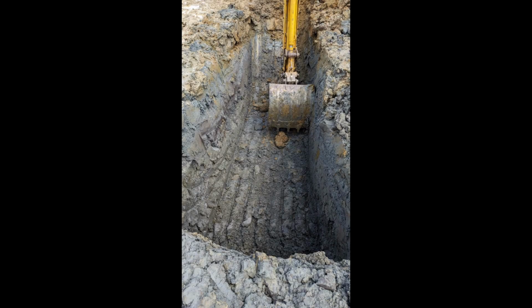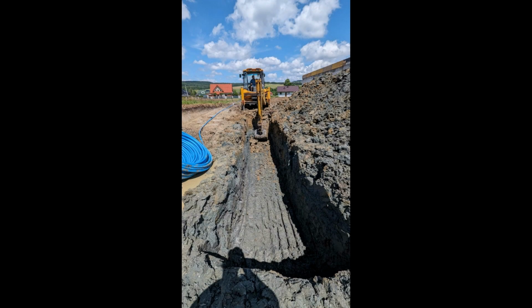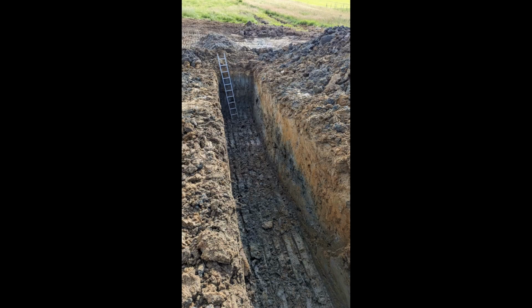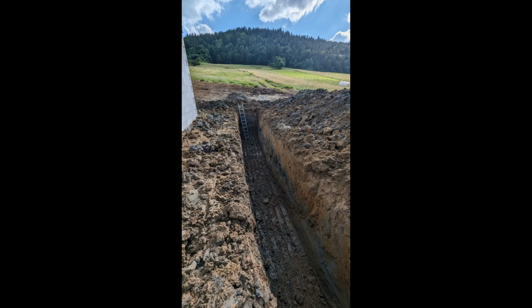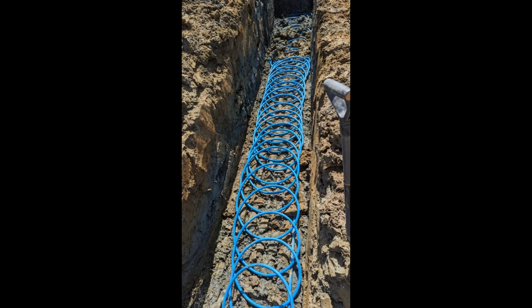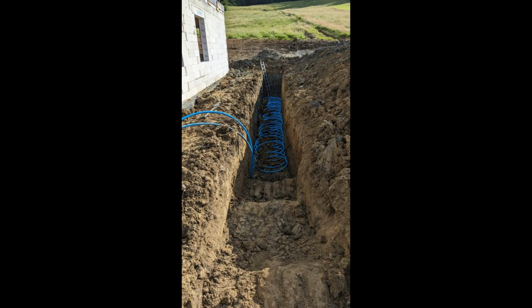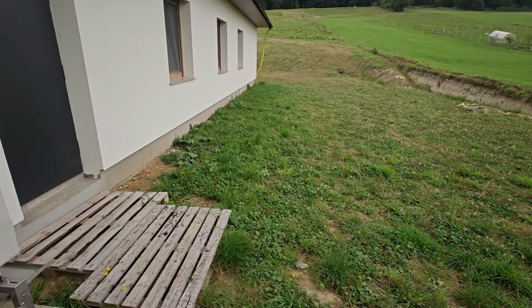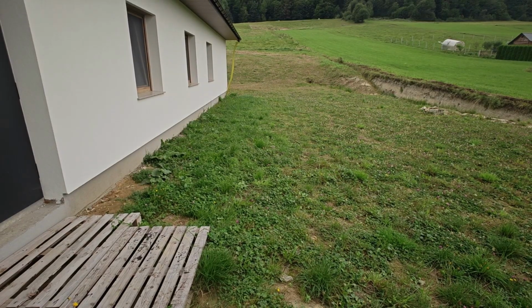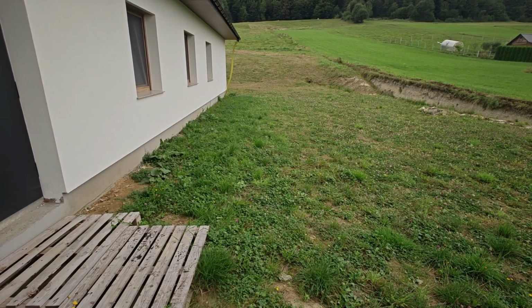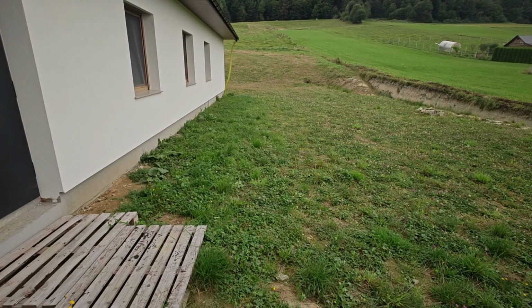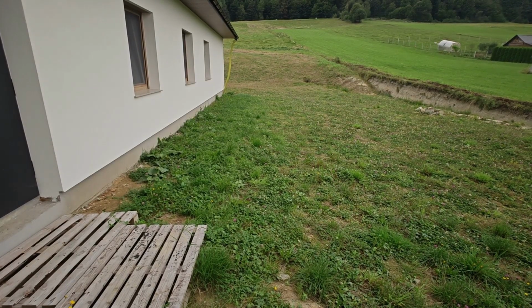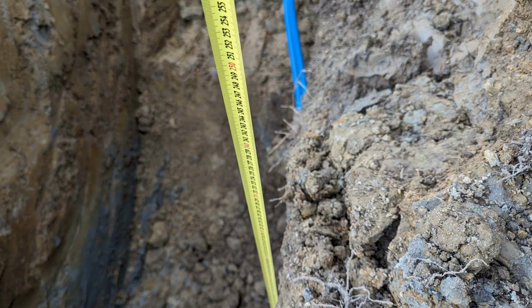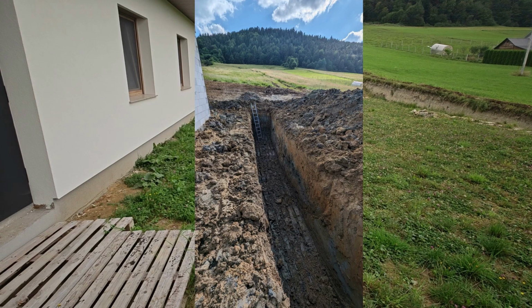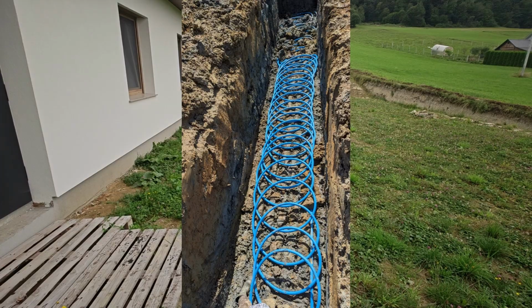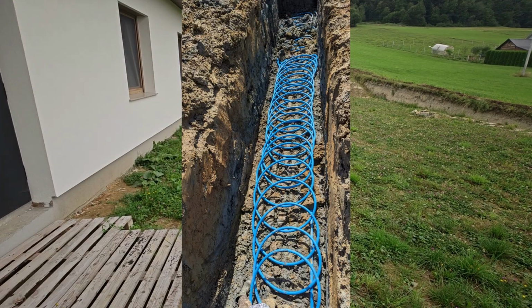The last elements of the system located outside are 2 loops from the glycol ground coupled heat exchanger. They each have a length of 200 meters. The material used for these loops is a PE water pipe, 40 millimeters in diameter, with a wall thickness of 3 millimeters. They are located here on the side of the building. Both loops on the approach to the building and where they enter the facade insulation layer are insulated to minimize heat or cold losses in the upper soil layers. The pipes are buried in trenches about 2.5 meters deep and approximately 15 meters long, with a width allowing them to be freely laid, as shown in the pictures.